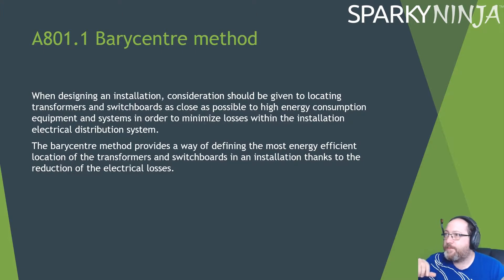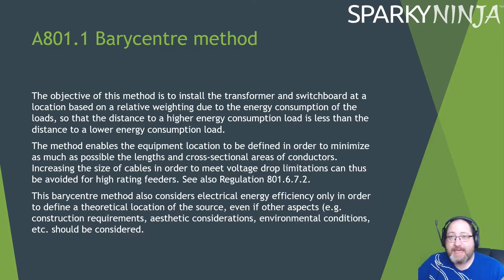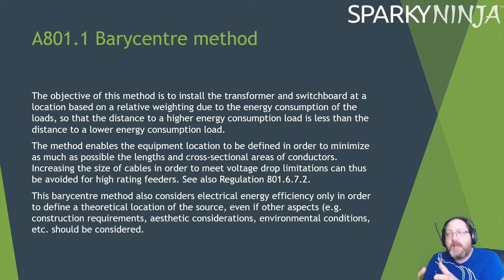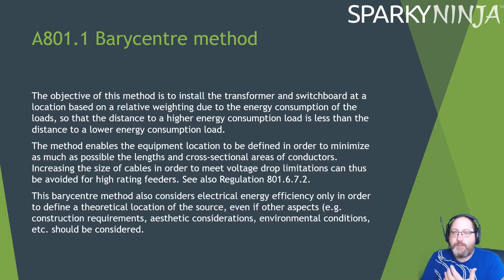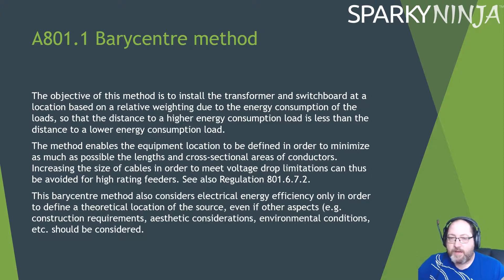The objective is to install the transformer and switchboard at a location based on a relative weighting due to the energy consumption of the loads, so the distance to a high energy consumption load is less than to a low energy consumption load. We're talking about the point of origin and the sub-main distribution — mainly the decision on where to put the plant room. The method enables equipment location to be defined to minimize conductor lengths, avoid oversized cables for voltage drop, and reduce energy losses.